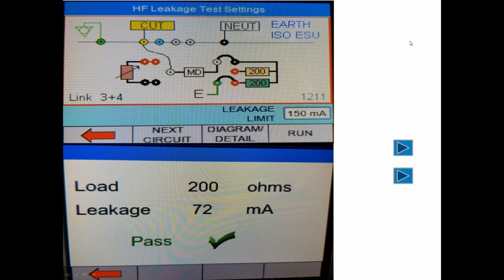Now, what I don't have here, and I sometimes demonstrate in my live presentations, is I'll take the test cable, the lead from the pencil itself, and I'll roll it into a coil, and I'll press it on top of the chassis of the Unitherm itself. So I'm adding in some inductance and some capacitance. And typically I can make a generator give a much higher reading, especially on the dissipative, where it would fail. I can typically get the leakage current up to 250 milliamps.